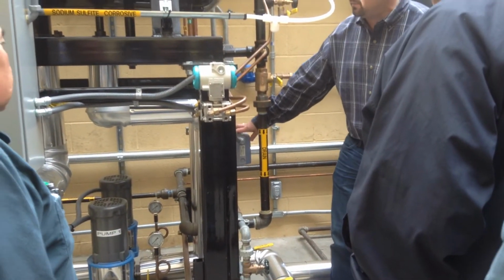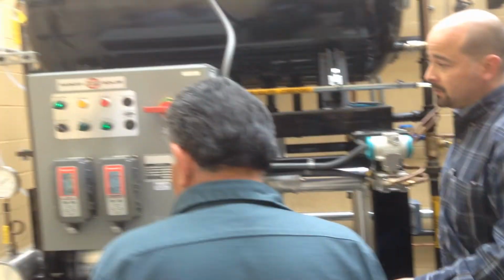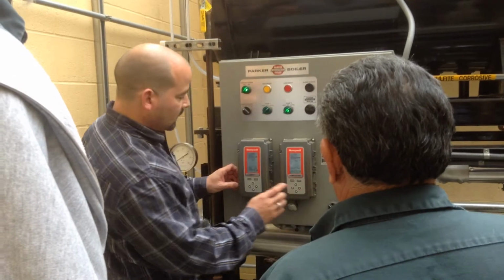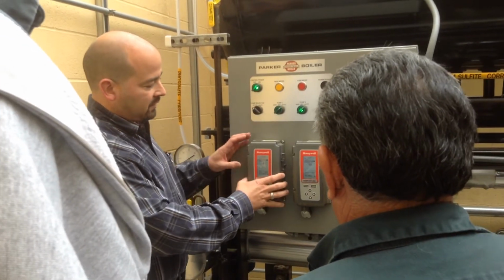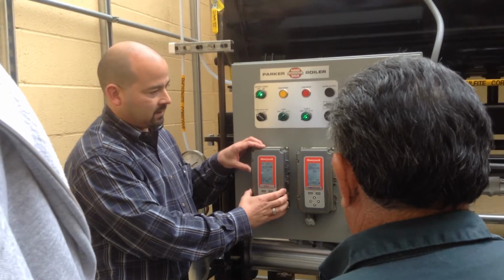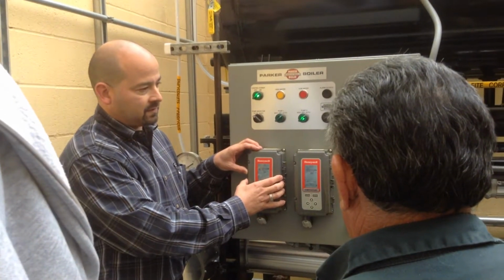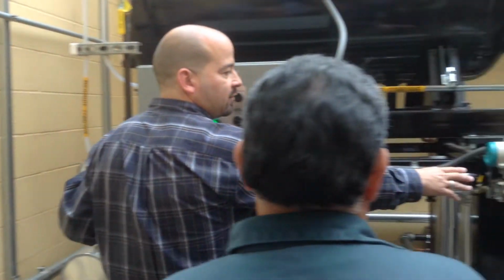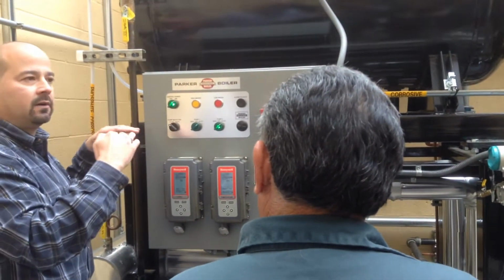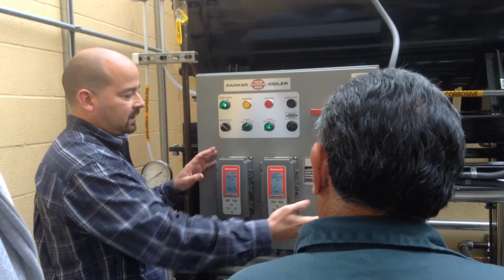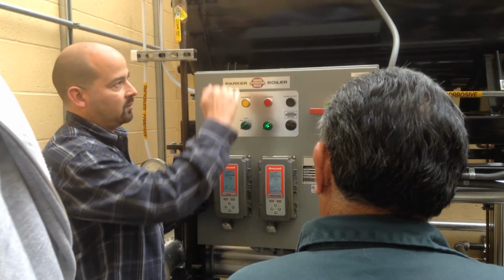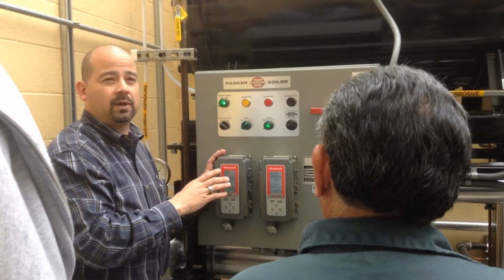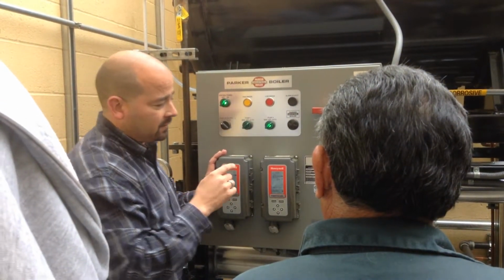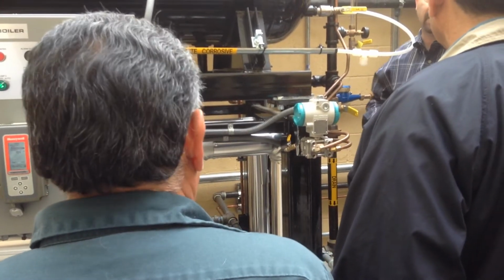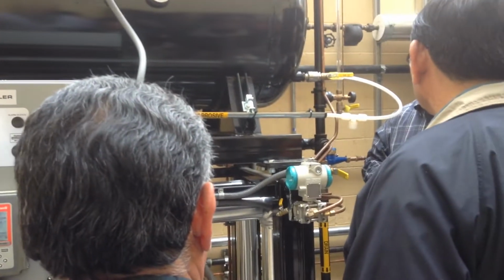So this modulated feed valve is controlled by this controller here. This controller is a Honeywell T775, and what it does is it takes a sample from a pressure transmitter, so it's measuring the weight of the water in inches of water column, sending the signal to the T775 to tell it where the water level should be. Works on a 4 to 20 milliamp principle. Then this sends a signal to this modulated feed valve to tell it how far open or how far closed it should be.